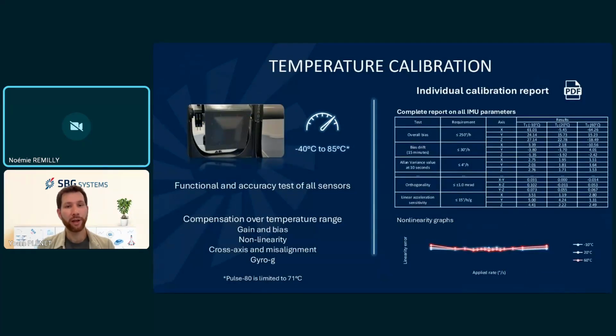Something very important for the IMUs is the calibration. When you're buying any IMU at SBG Systems, it's been individually calibrated. This calibration is what really allows us to guarantee the performance level of all our IMUs, because during this calibration, we do a full compensation of the various errors of the IMU. And this is also the final test to make sure that the IMU meets the performance level that we define. But I'm not going to go into a lot of depth on this topic for now, because Emric is going to cover this with a lot more details in the coming slides.